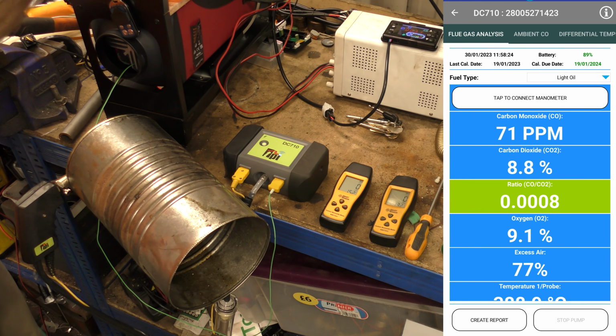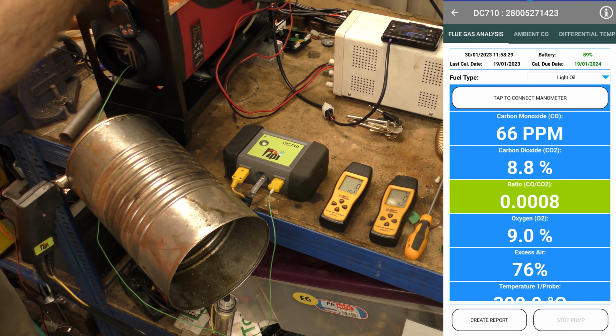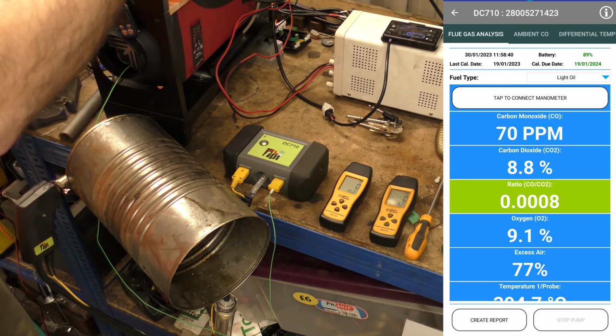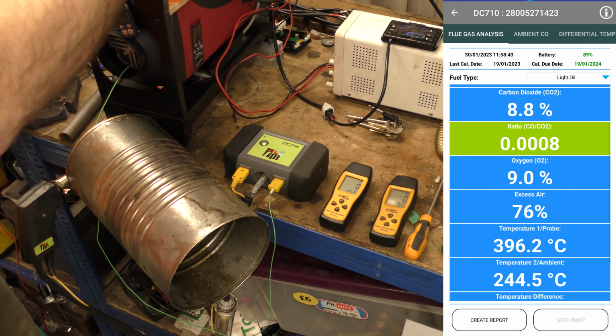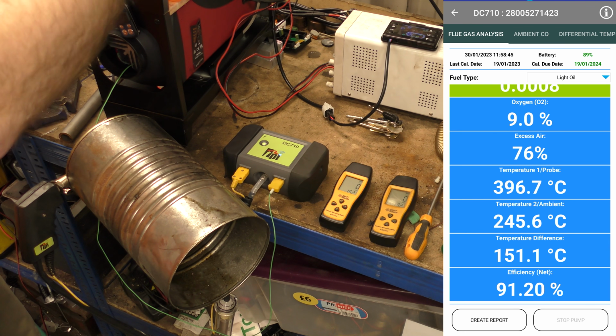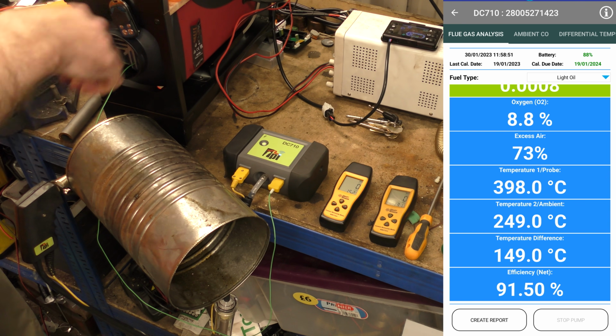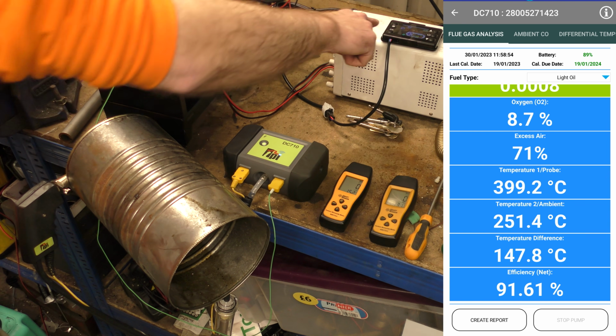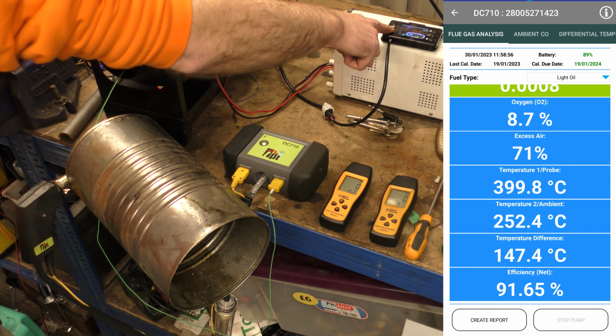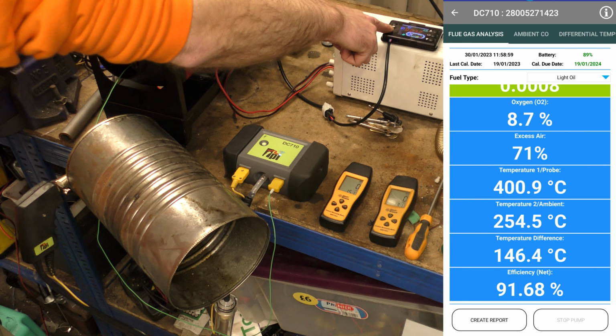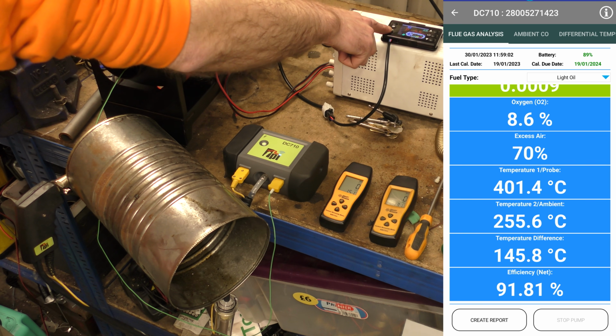Okay, so the TPI is showing us anywhere between 71 - oh there it goes down to 68, 66, 65. Well, we'll just call it 70-ish parts per million carbon monoxide. Carbon dioxide 8.8%, oxygen 9%, excess air 76%, and our probe temperature and our actual outlet air temperature, well, the housing temperature - 250. Does this one show... no, this controller doesn't show housing temperatures, unfortunately.